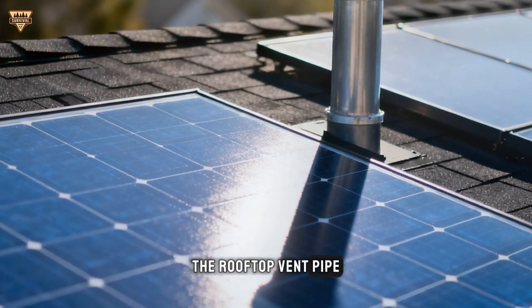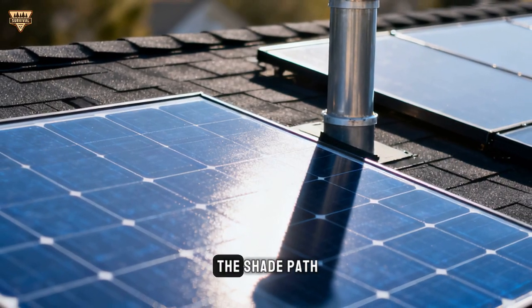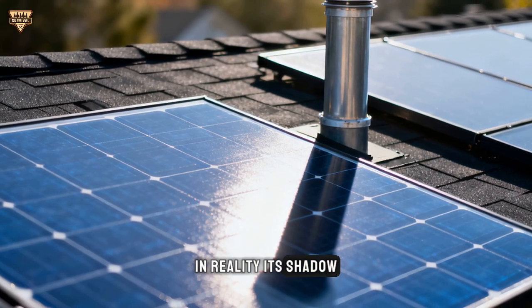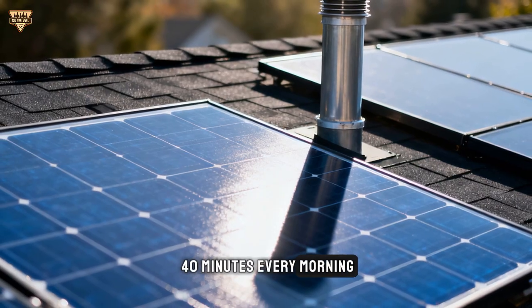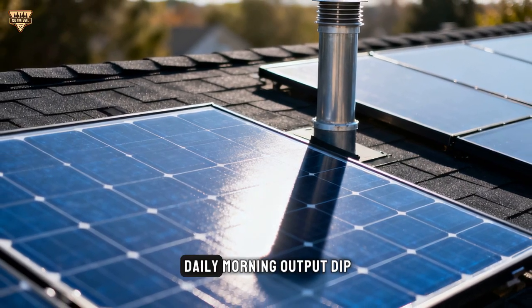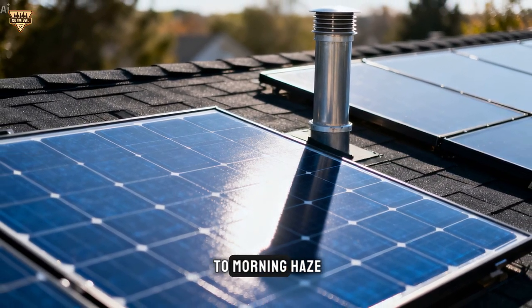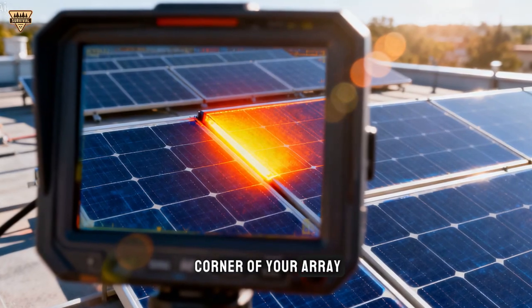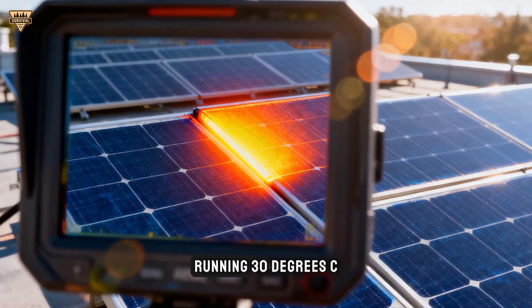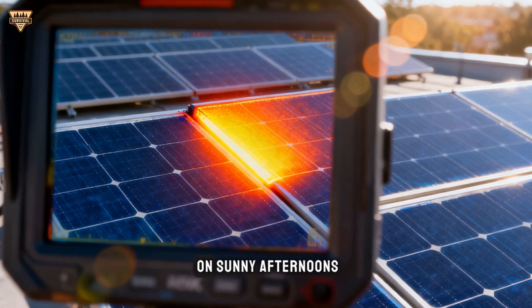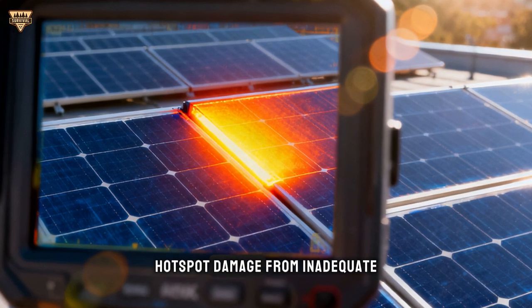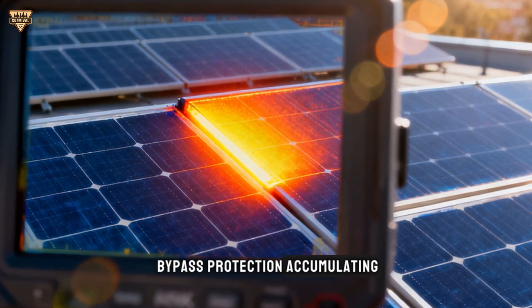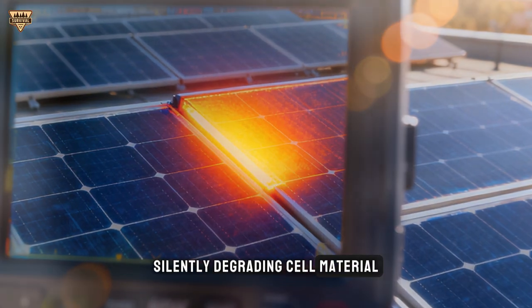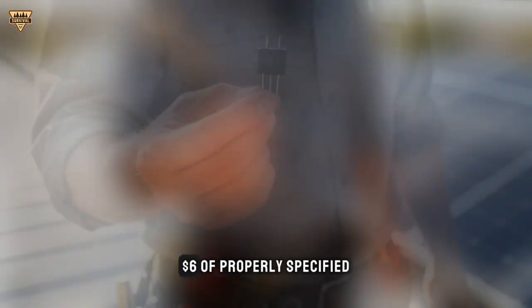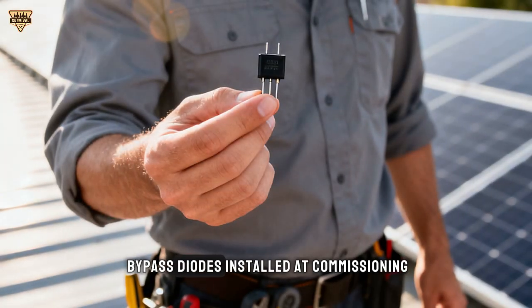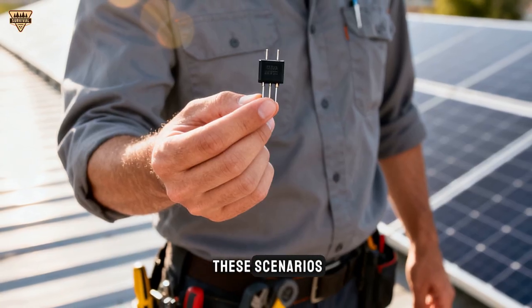The rooftop vent pipe that your installer assured you was not in the shade path. In reality, its shadow crosses one panel for 40 minutes every morning. Your monitoring shows a daily morning output dip you have been attributing to morning haze. The panel in the corner of your array that your thermal camera app shows running 30 degrees C hotter than adjacent panels on sunny afternoons. Hotspot damage from inadequate bypass protection. Accumulating silently, degrading cell material that cannot be restored. $6 of properly specified bypass diodes installed at commissioning prevents every one of these scenarios.